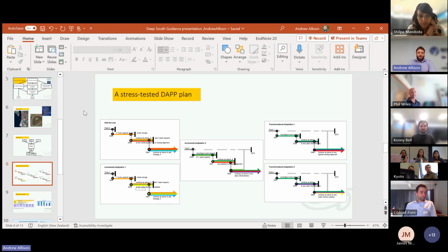So for the next couple of slides, I'll talk to the Petone Seaview plant case study. We ran a Monte Carlo analysis of 150,000 iterations on that model to identify what combinations of adaptive actions were successful at allowing the plant to remain on site until 2100 and beyond. That plant's current design life is until 2080. So we identified 5 robust strategies that would allow this, with the timing of implementation of different adaptive actions determined by the rate of sea level rise.